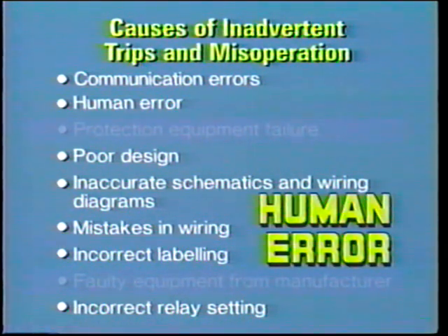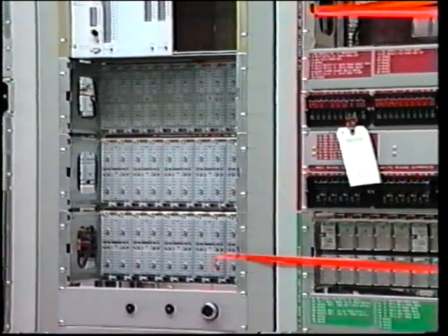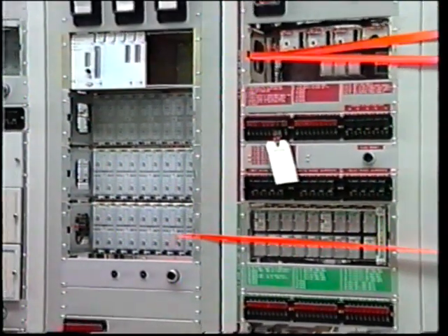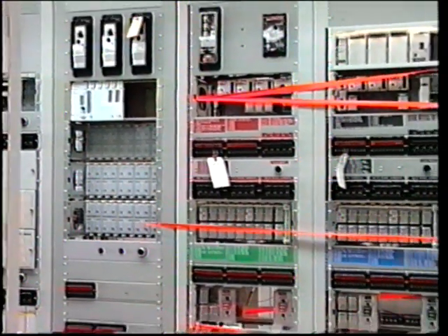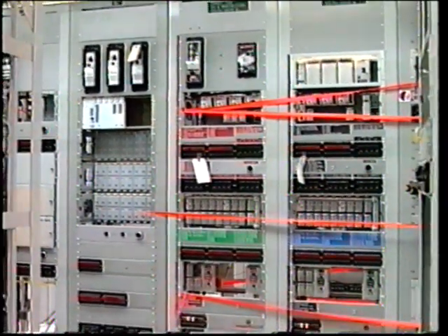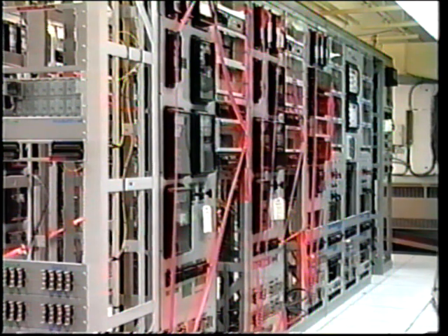For example, incorrect wiring, poor design, incorrect relay setting, and so on. The most common causes of human error are lack of attention to detail, not being fully prepared for the job, taking shortcuts, making assumptions, especially on routine jobs, and not following procedures. Clearly, there are many potential areas where errors can creep into the protection scheme, and much of this can occur during the installation stage. This could be during construction of a completely new facility or perhaps modification of an existing station.